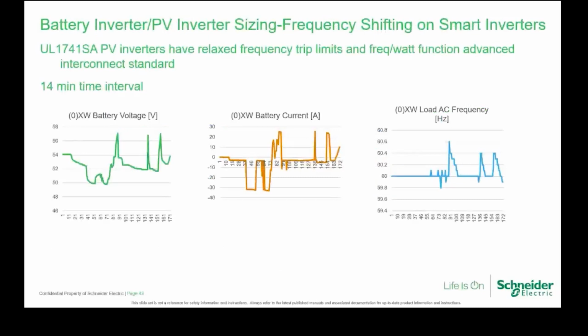Frequency shift on smart inverters. These are the UL1741 SA PV inverters, which have relaxed frequency trip limits and frequency-watt functions, an advanced interconnect standard. Basically, same sort of thing. The battery voltage rises, but the battery current will follow through what the requirement is, and so the AC frequency changes as required. The profile follows more closely what the battery charging requirements are, because it's smart enough to detect that, okay, I need this much energy, I'm going to talk to the string inverter using frequency shift, so that the current available is going to match what the PV inverter is pushing out.